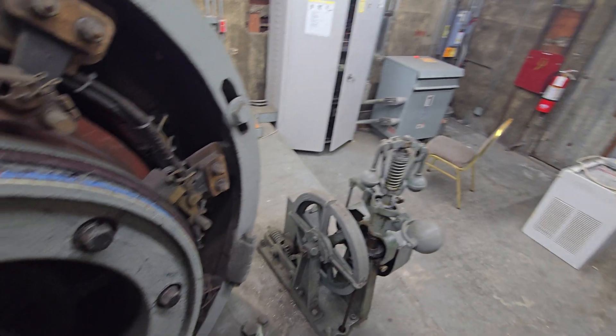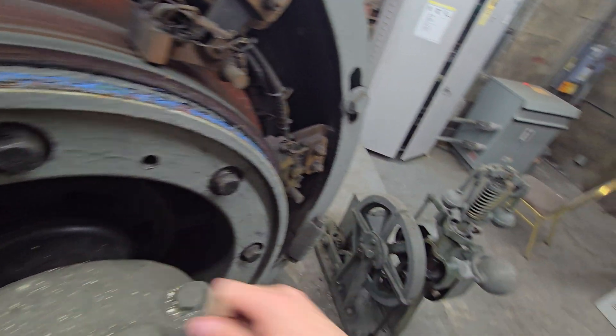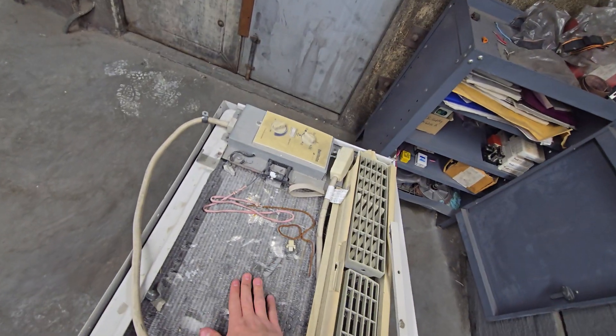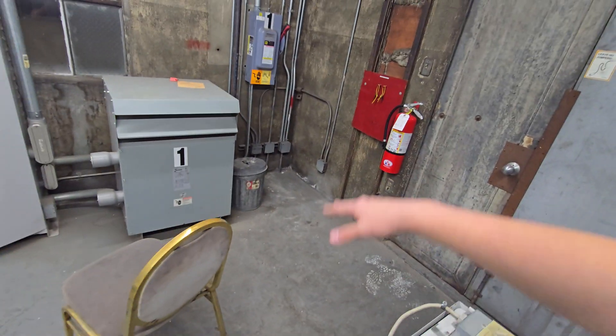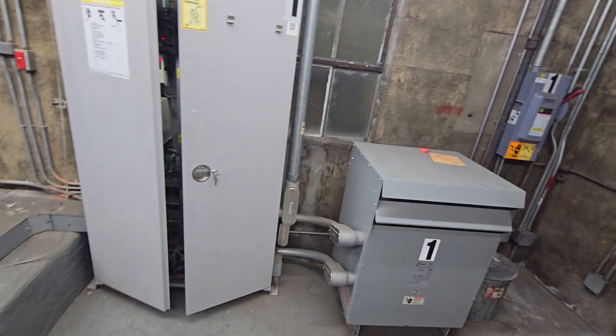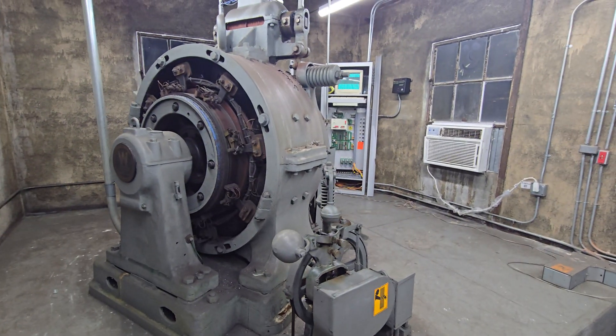That isn't a bad bearing — that's actually coming from the governor. All of them are making that same noise. It's just how these governors behave. And because they use these crappy window units, these things keep failing. The service car machine room window unit failed and it's not working — well, it's working a little, but pretty much just cooling it down to outside temp. That's about it, which obviously is not going to be doing much.